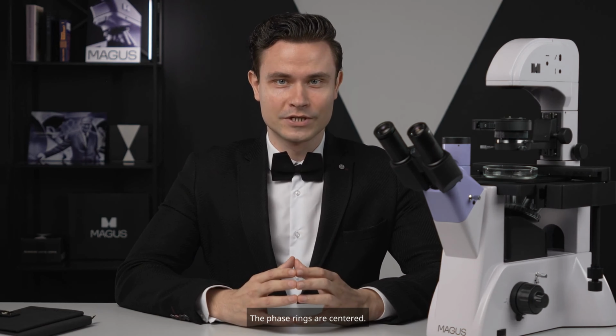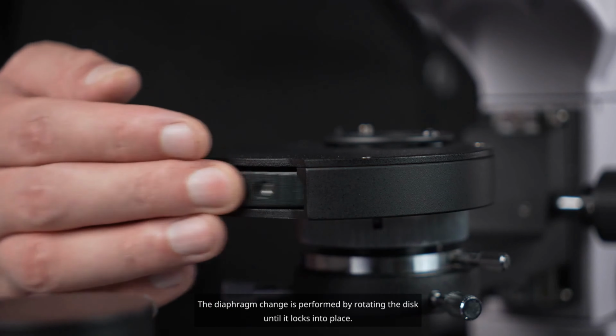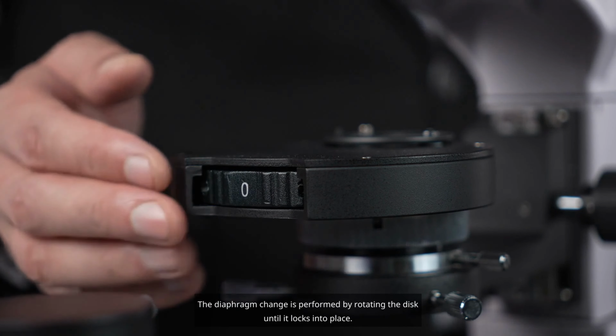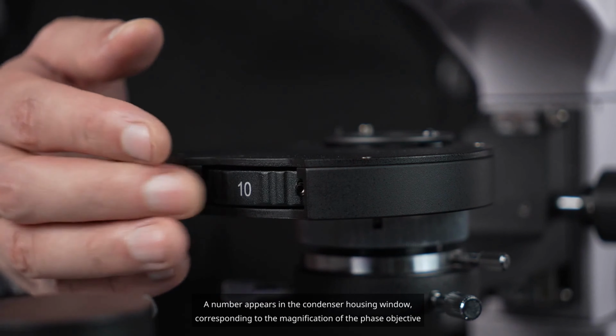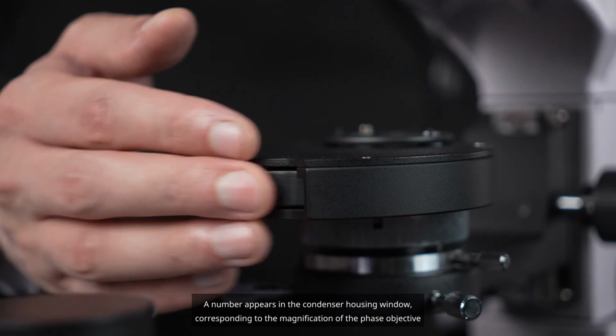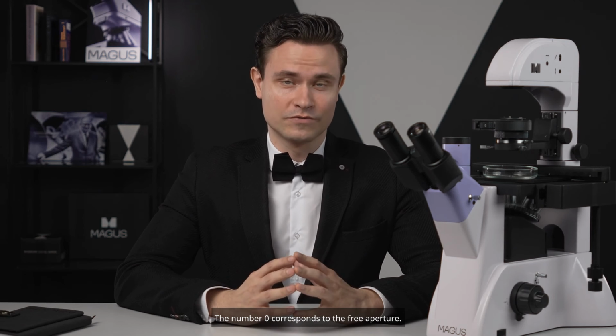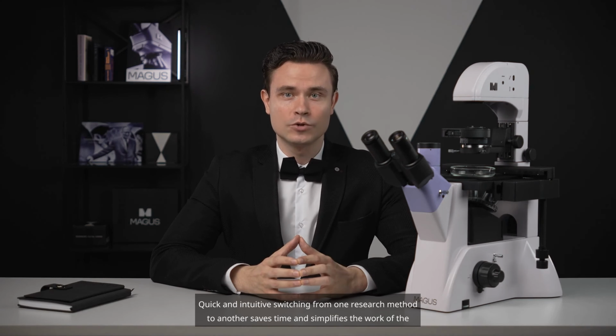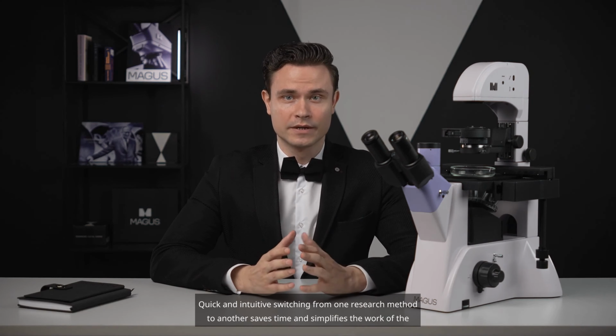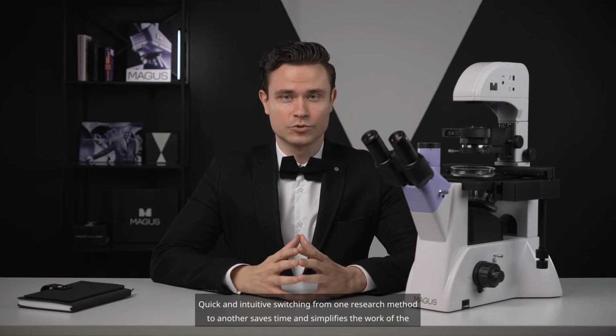The phase rings are centered. The diaphragm change is performed by rotating the disc until it locks into place. A number appears in the condenser housing window, corresponding to the magnification of the phase objective being used. The number 0 corresponds to the free aperture. Quick and intuitive switching from one research method to another saves time and simplifies the work of the researcher.